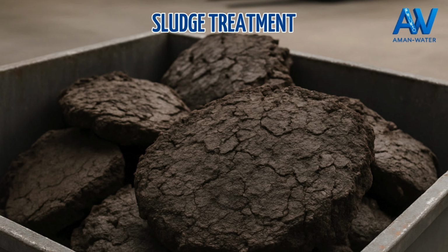Throughout the process, several technical parameters play an essential role. Dry solids content, which determines the amount of dry matter. The retention time in digesters, often between 15 and 30 days. And the operating temperature, generally around 35 to 38 degrees Celsius for mesophilic digestion. Once thickened, stabilized, and dewatered, sludge is ready for its final destination. Depending on its quality and composition, it may enrich soils, produce energy, or be eliminated when it is too contaminated.